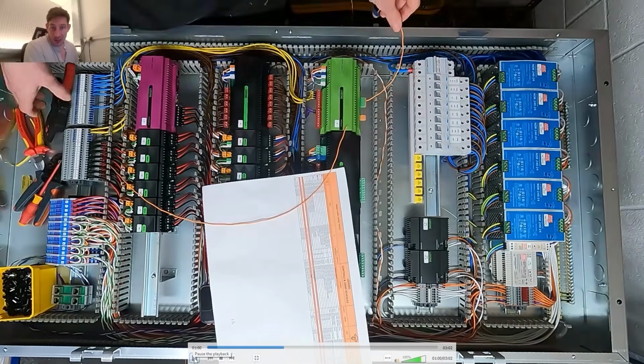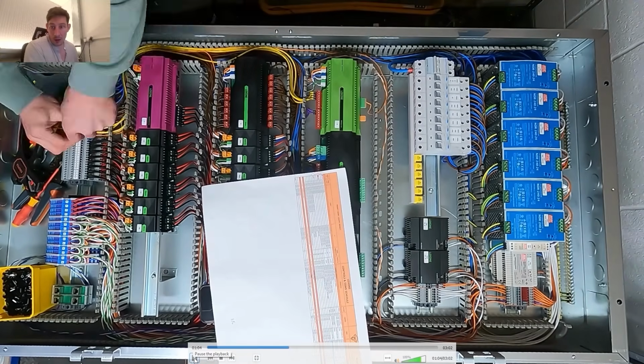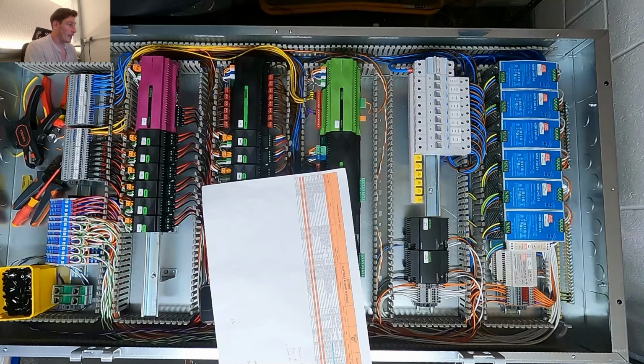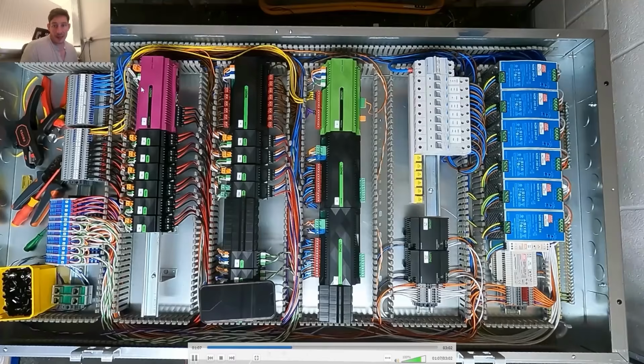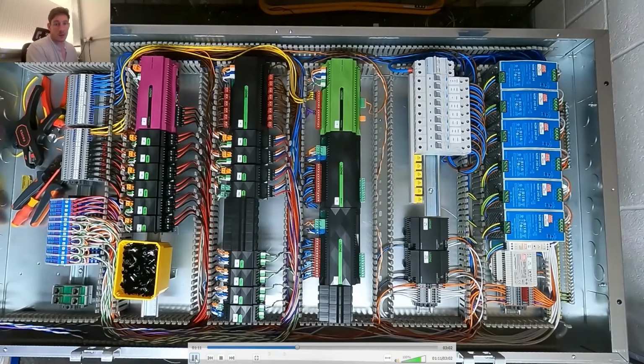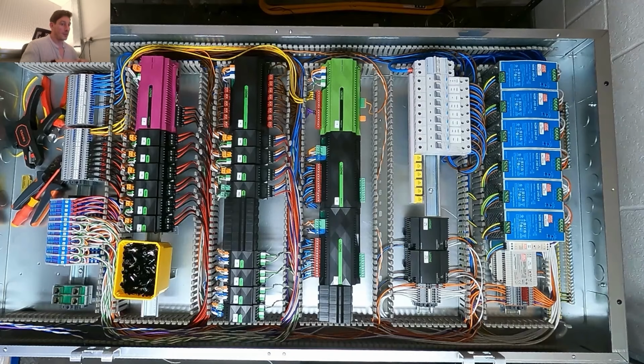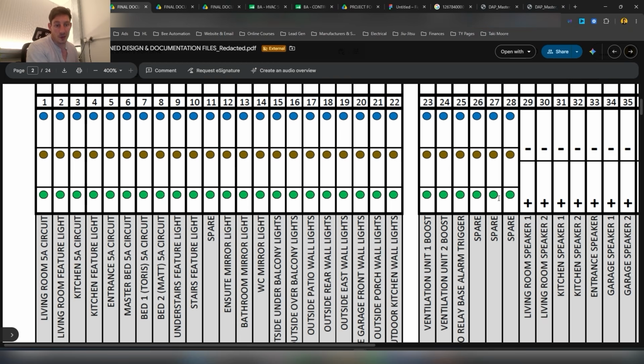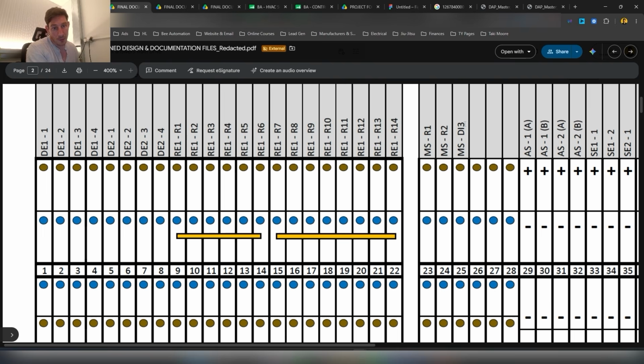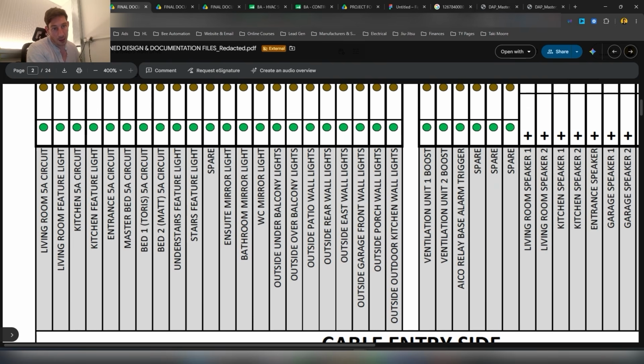Now what you can see is we're doing digital inputs for - let me just double check - yeah, this is the digital input for the AICO relay based alarm. So if the fire alarm triggers, the Aico fire alarm, it can send a signal back into the Loxone control system, we can detect that, and then program a load of things off the back of it, like turn the lights on, open the blinds, open the windows, unlock the doors, etc. Because it's like an emergency, we want certain things to happen off the back of that, so we detect it through that digital input signal. Mini server digital input 3 is that ACO relay based alarm trigger.